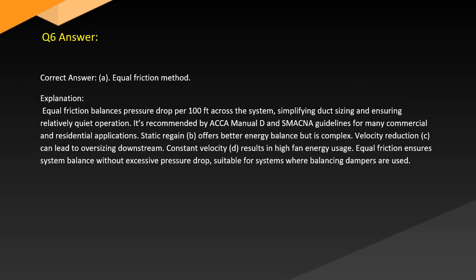Answer. Correct answer A. Equal friction method. Explanation: equal friction balances pressure drop per 100 feet across the system, simplifying duct sizing and ensuring relatively quiet operation. It's recommended by ACCA Manual D and SMACNA guidelines for many commercial and residential applications.